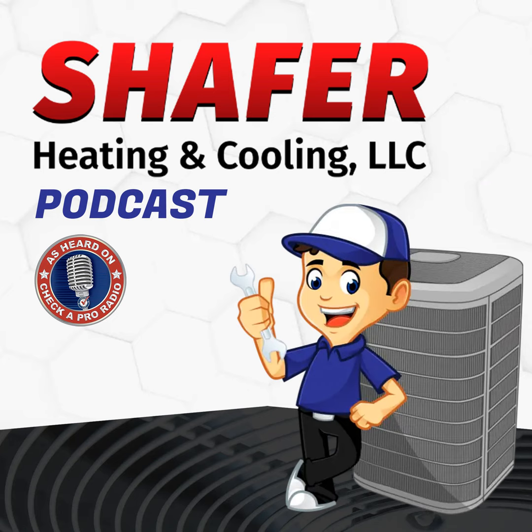There are other filter options, and that's when we start getting into media air filtration as well as air cleaners. Those are typically going to take maybe a couple of modifications on the system, nothing major, nothing sketchy, things that we can take care of. It's no big deal. But now we're going to start actually cleaning the air and keeping the system clean. That's going to be some big, thick media filters that can be installed in your system. We have to size those appropriately because, yes, there is more pressure drop that comes through it, but we can catch more particulates. Or you can put in electronic air cleaners that positively charge the particulates in the air to cause them to attract and catch in that filter.